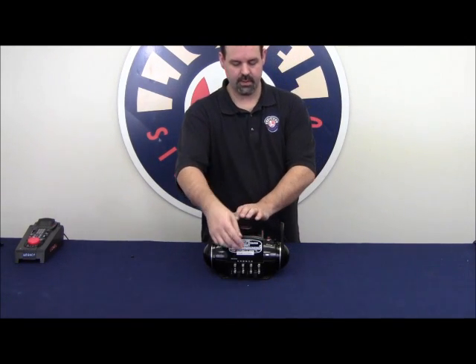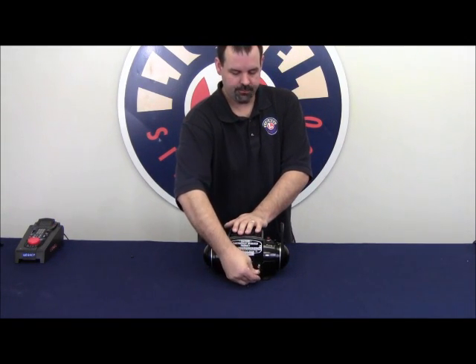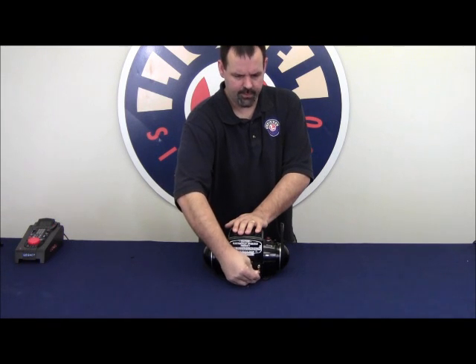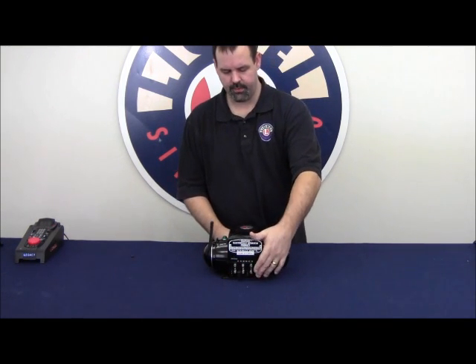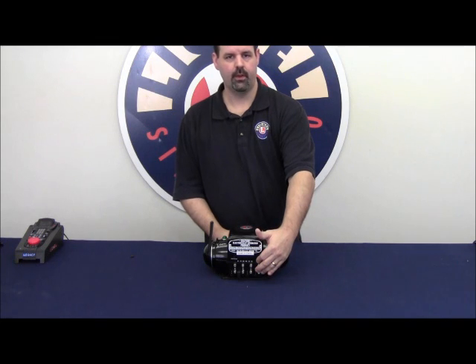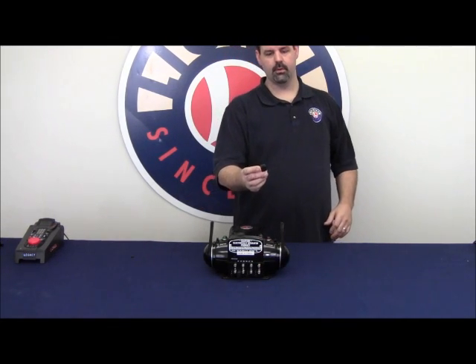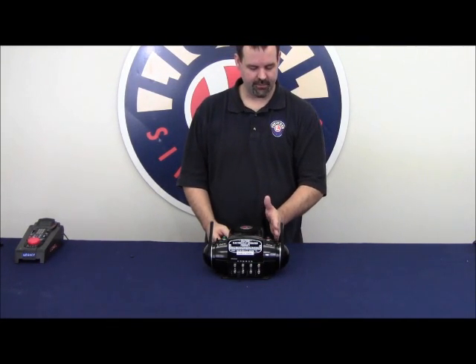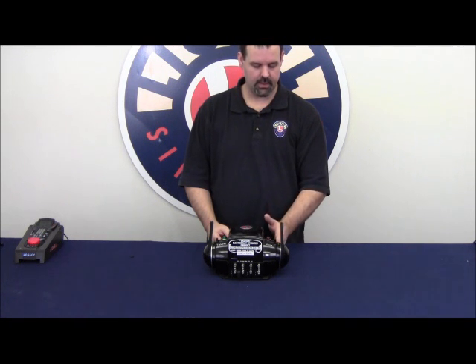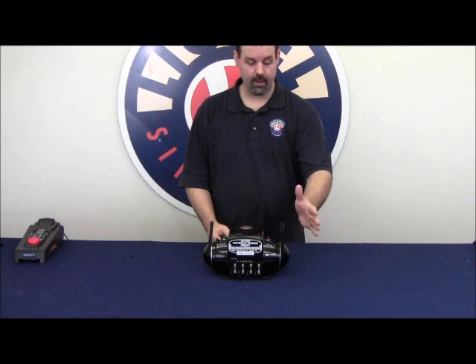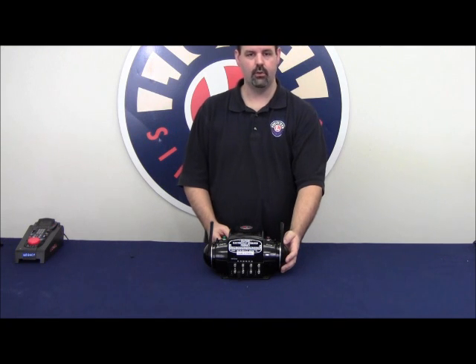The way the ZW is designed is you can remove this jumper in the C and U position, or D and U position, and install another powerhouse here. By removing these jumpers, you're giving a full 7.5 amps to the C and U throttle, and then another full 7.5 amps to the D and U throttle.